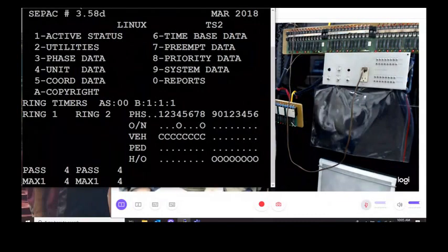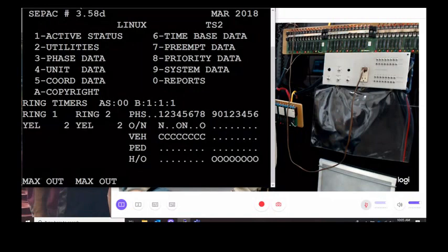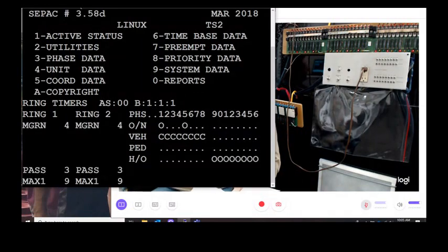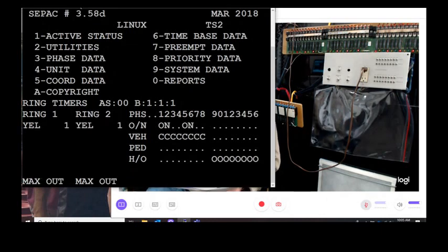is that lower screen. And then I would say, look in the lower right-hand corner. And basically the lower right-hand corner will give us some type of message. And as I create the faults, then you will better understand what I'm talking about. It's going to tell us stop time, cabinet diagnostic flash, something like that. So from that vantage point, I can kind of start going in a different direction.